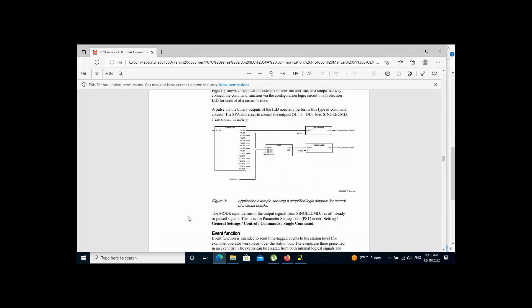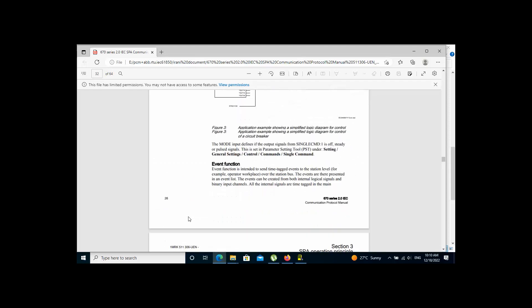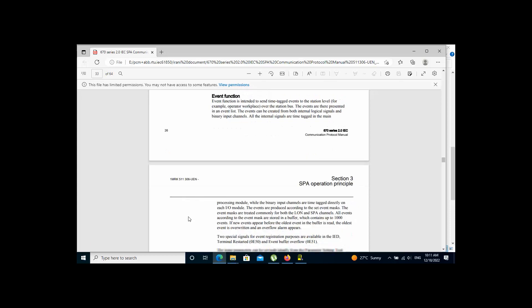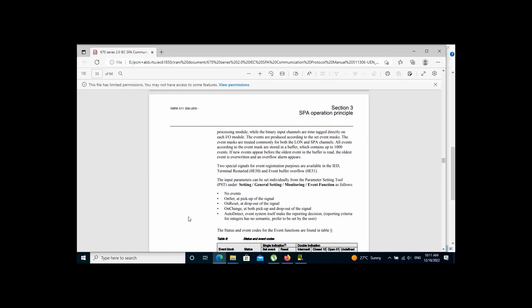As we went through the manual, we come to this page. As I said, event function is intended to send time-tagged events to the channel at the station level — for example, operator workplace over the station bus. The events are presented in an event list. These events can be created from both internal logic signals and binary input channels, which means that in order to send this signal, we need to connect it to an event block.